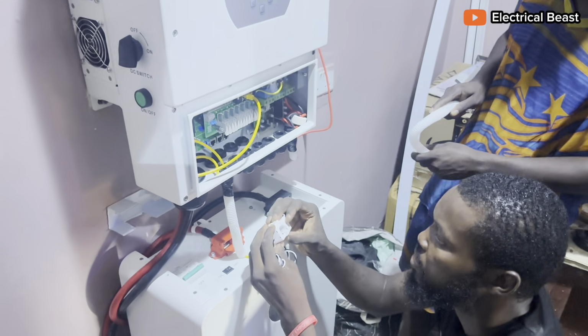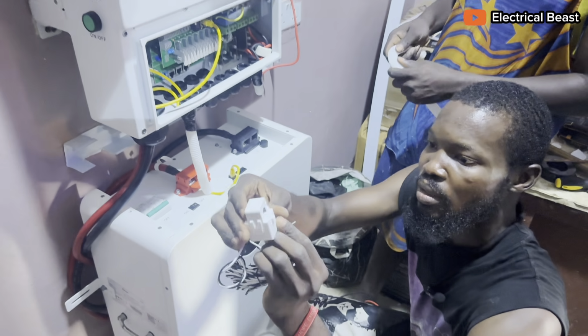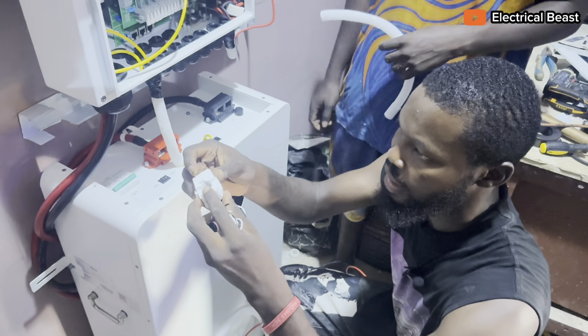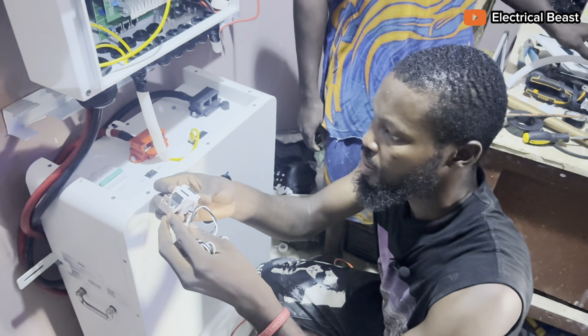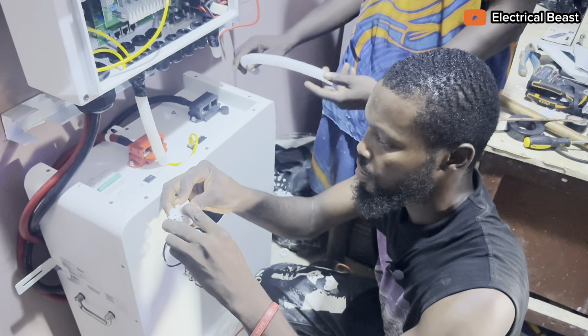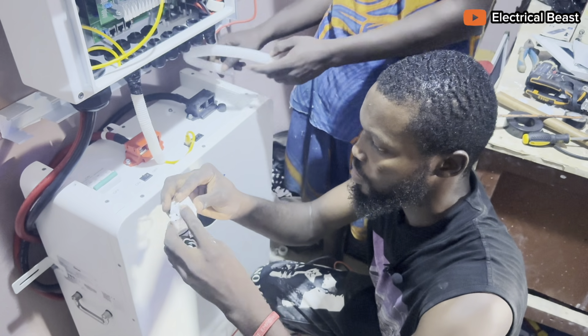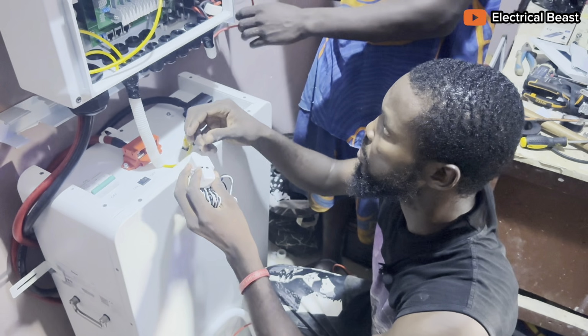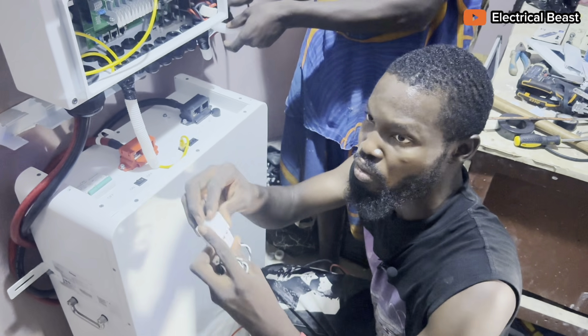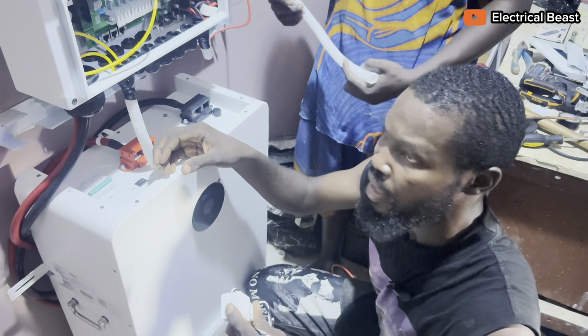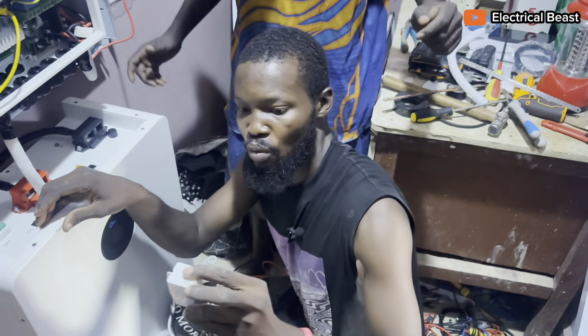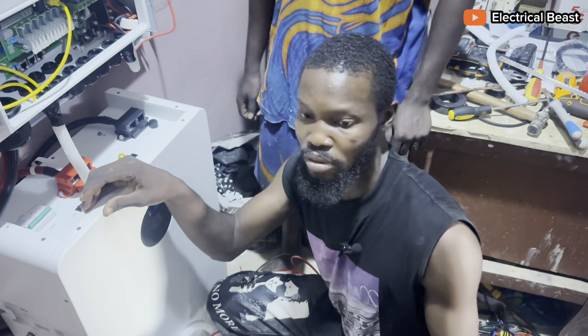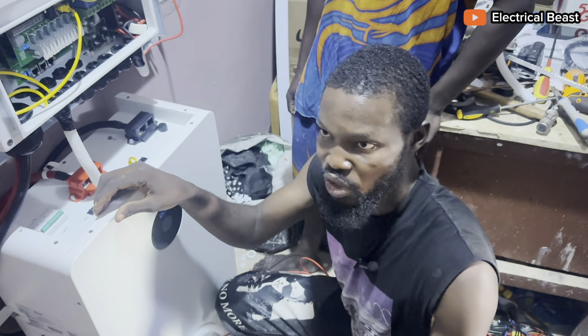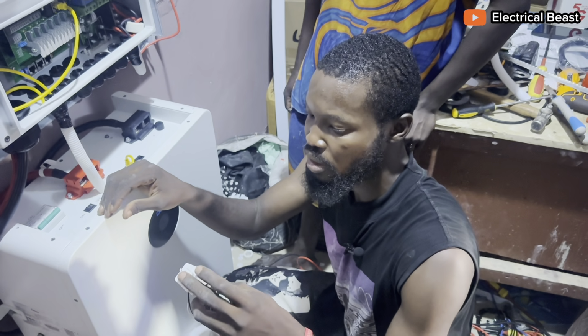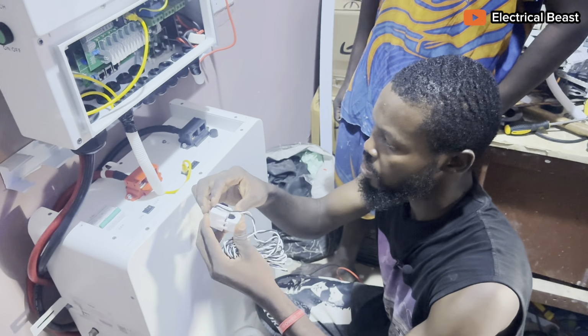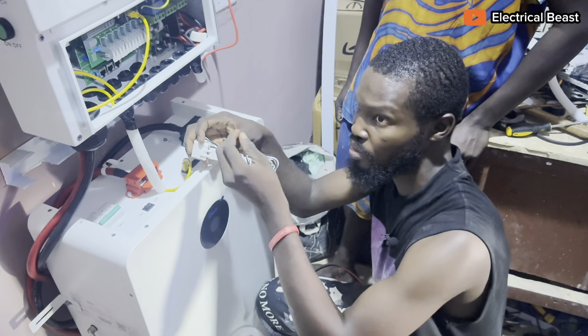There's this device that came with this inverter. This is a current transformer. It measures current, and you can clamp it on the AC side, the load side or the grid side of the inverter, to measure the current that goes into the inverter or the current that goes out of the inverter. Now this inverter has a feature called export to grid, where you can sell power to the grid. But in this case, we don't want to use that feature, so we need to use the CT to block that feature, because by default the inverter sends power to the grid.